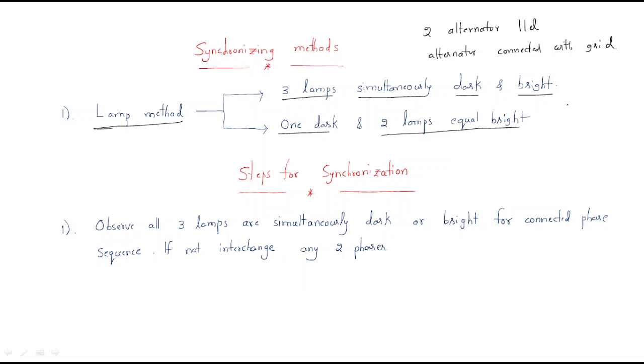When connecting, one lamp is between R phase and R phase, one lamp is between Y phase and Y phase, and one lamp is between B phase and B phase. When the supply is the same, all three lamps become simultaneously dark or simultaneously bright.